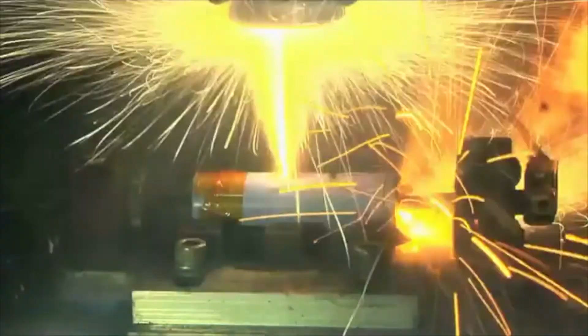This is the most reliable way to force it into runaway in a short time period, but we could also see a manufacturing defect - something as simple as a speck of dust on the membrane or separator causing an internal short circuit or damage. If you dent that battery, it may not happen right away, but it creates a friction point, which starts to drive the internal temperature up.